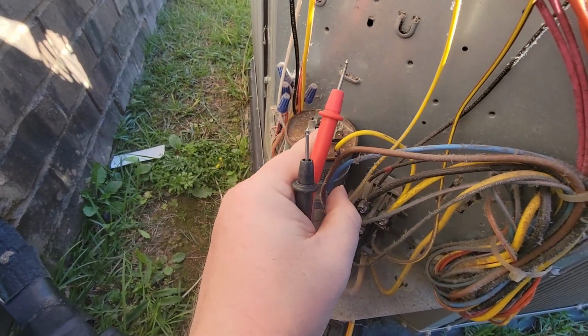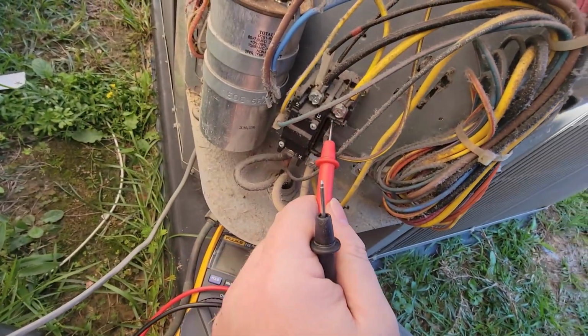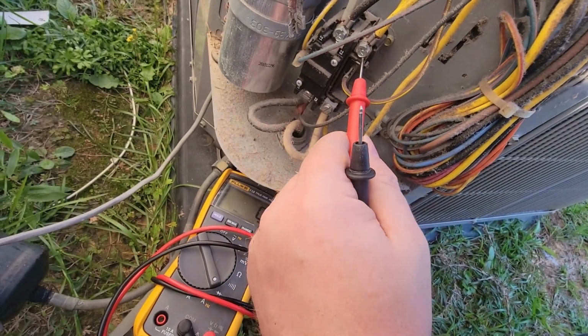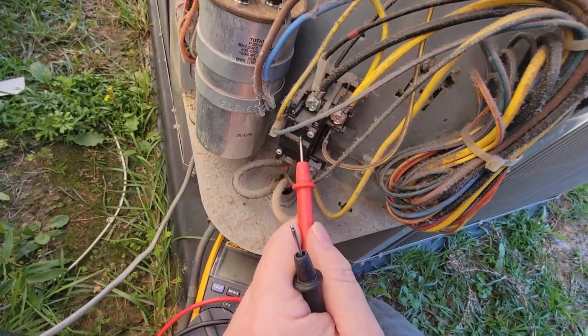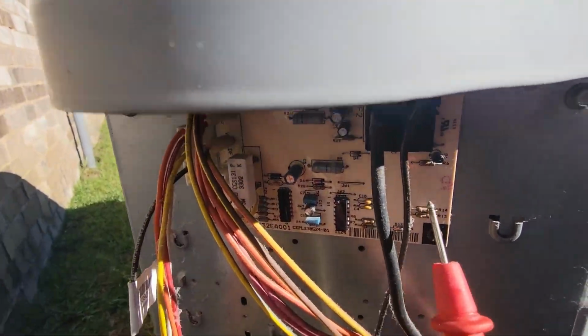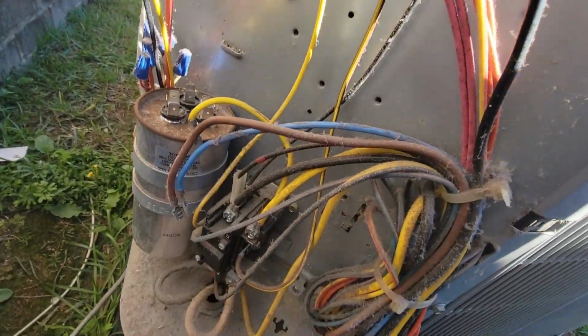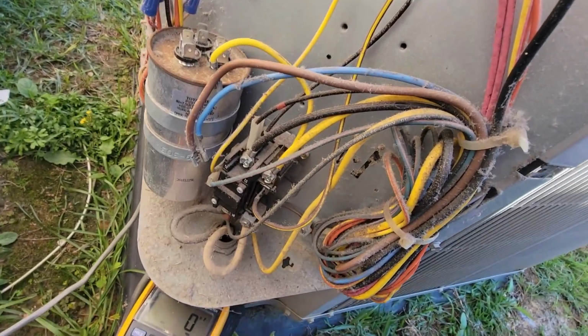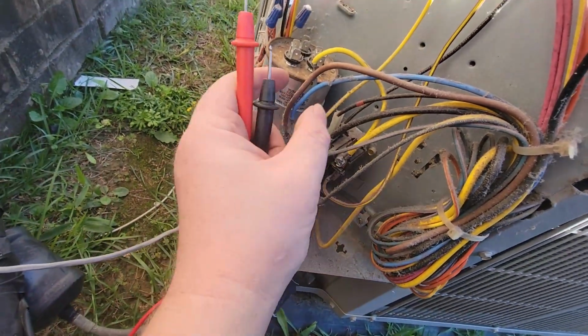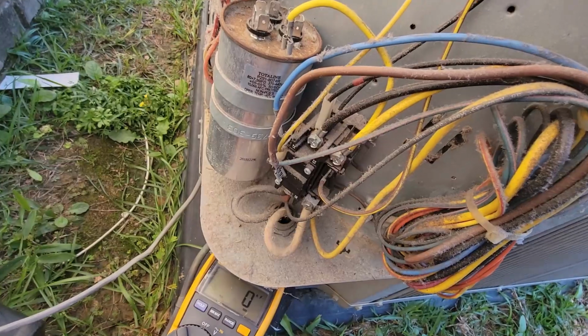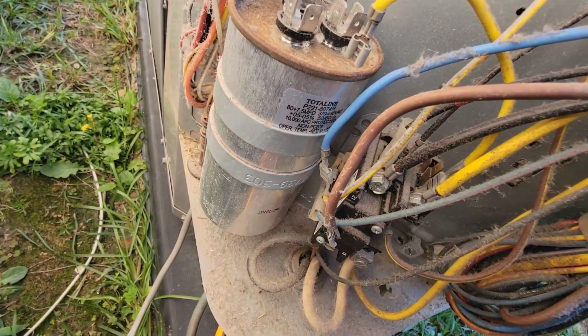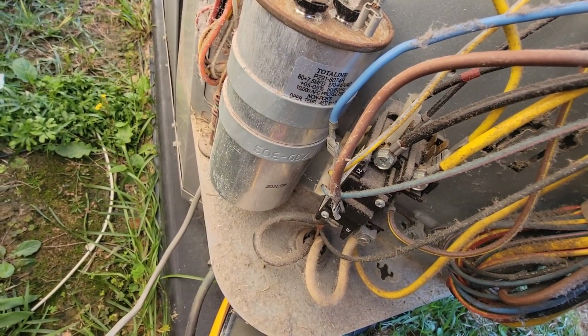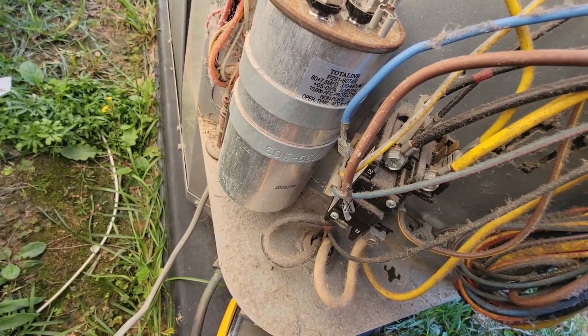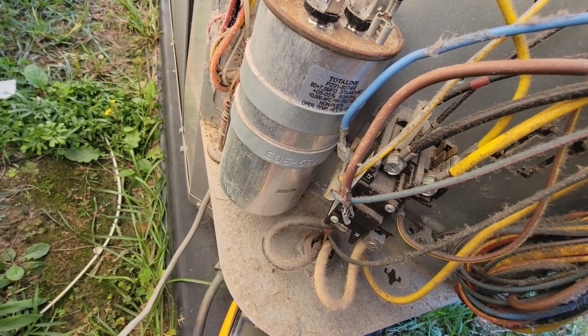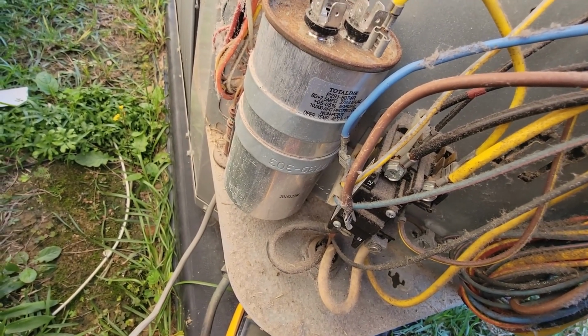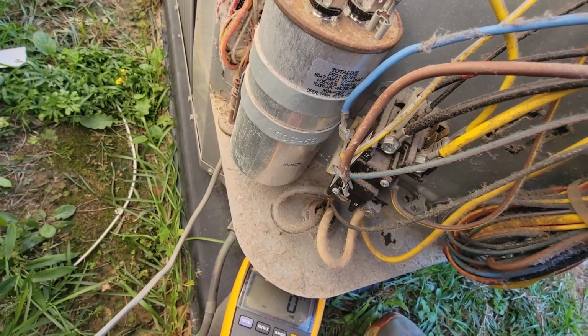Okay, yellow from this leads to this fuse/relay, whatever this terminal board is here. I believe that's a relay. We also got another relay sitting up there. Those could be two failure points. We'll be cleaning up those terminals, but I'm going to check, verify the capacitance. We see that we have an 80 microfarad cap and a 7.5 microfarad cap. Both of those should be plus or minus 5%.